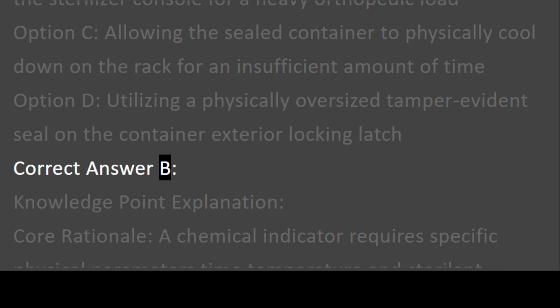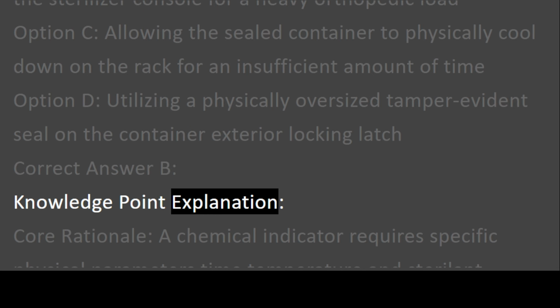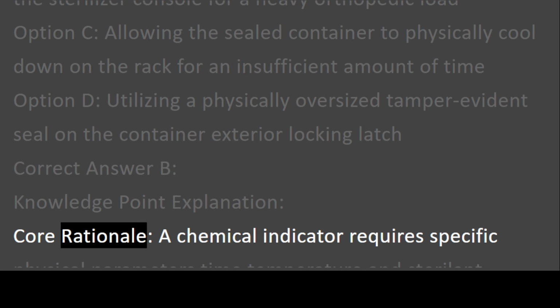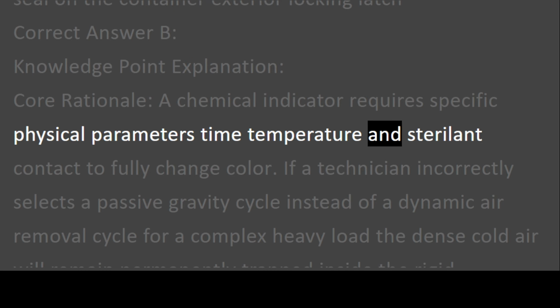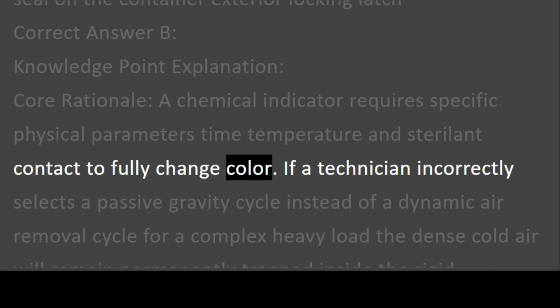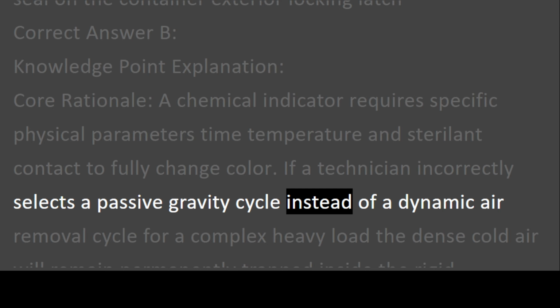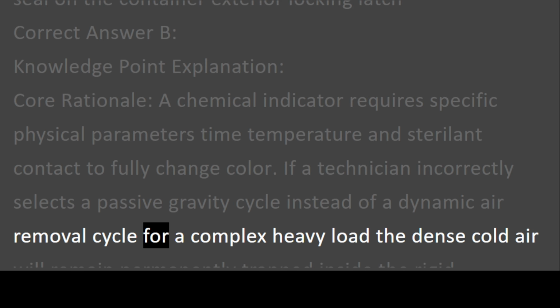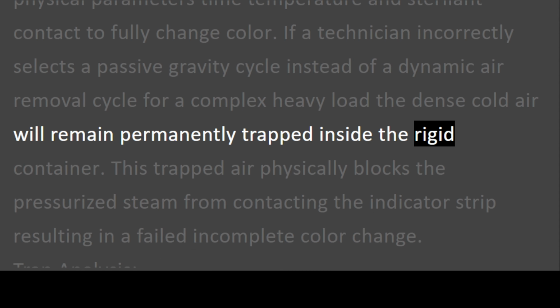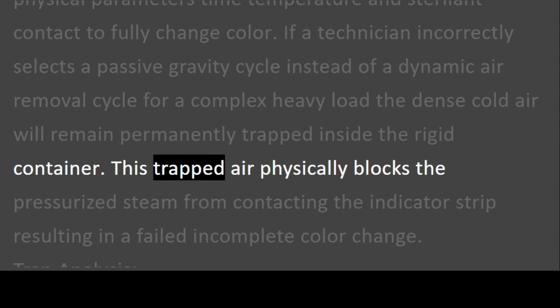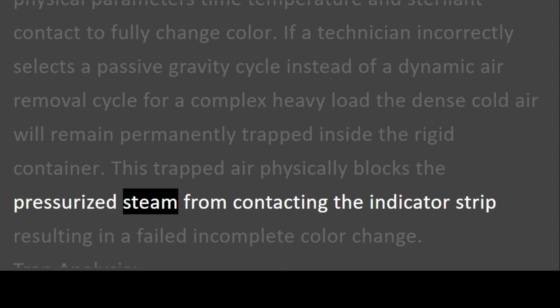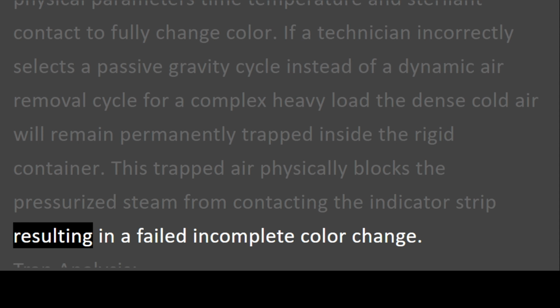Correct answer B. Knowledge point explanation. Core rationale. A chemical indicator requires specific physical parameters, time, temperature, and sterilant contact to fully change color. If a technician incorrectly selects a passive gravity cycle instead of a dynamic air removal cycle for a complex heavy load, the dense cold air will remain permanently trapped inside the rigid container. This trapped air physically blocks the pressurized steam from contacting the indicator strip, resulting in a failed, incomplete color change.